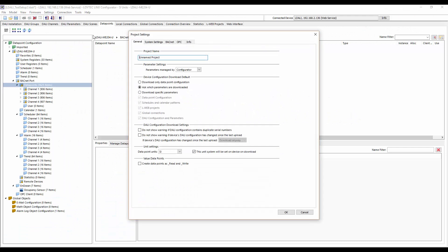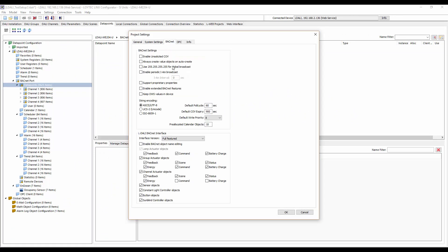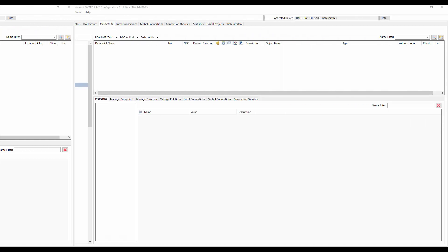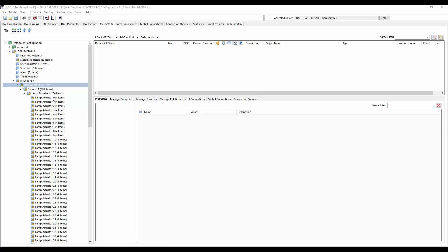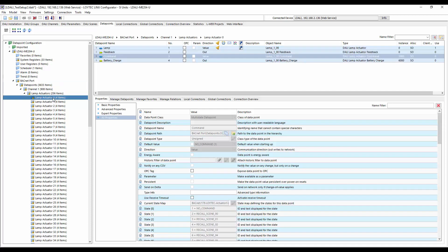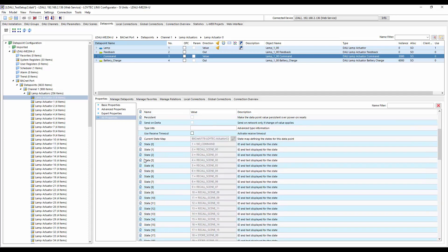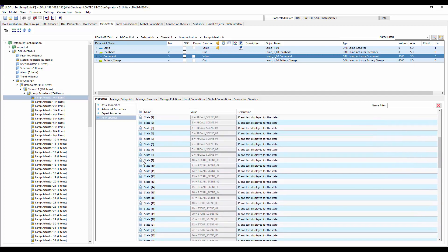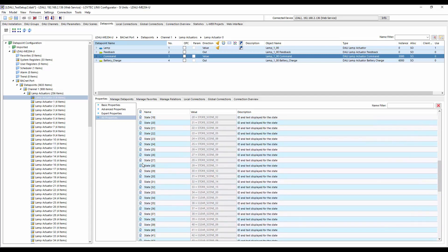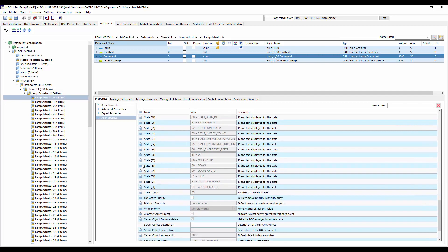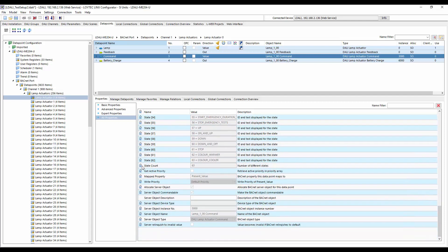The LDALI's project settings allow configuring which BACnet objects are available. This also allows removing BACnet objects not required in a specific application, thus reducing the number of objects on LDALI's BACnet interface. New objects were added to the BACnet interface. One of those objects is the multi-state output object. This object allows to issue commands to single DALI ballasts, DALI groups or DALI channels, like for example, start stop emergency test, burn in or to change color temperature.